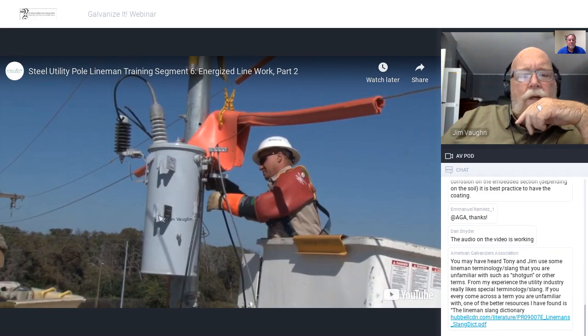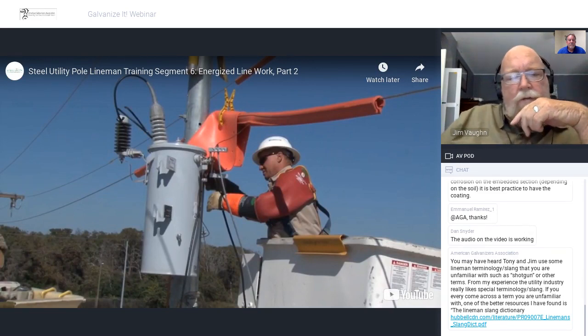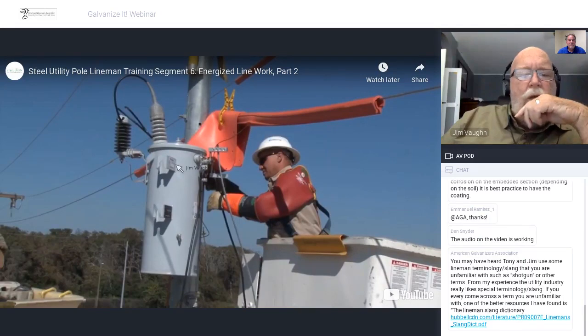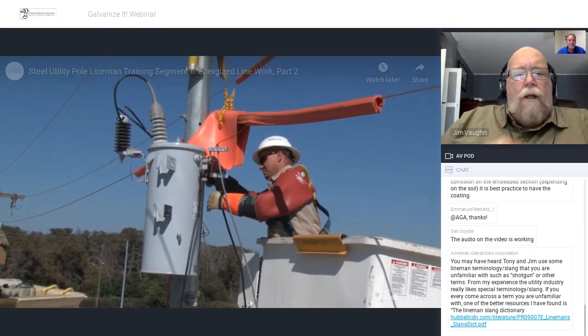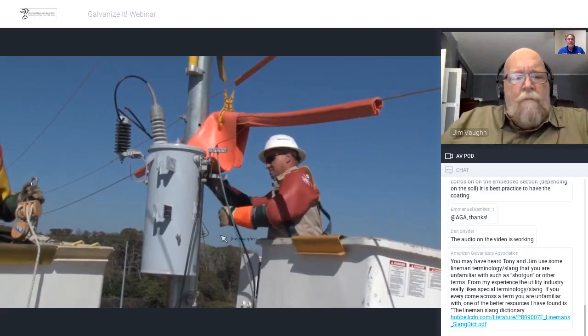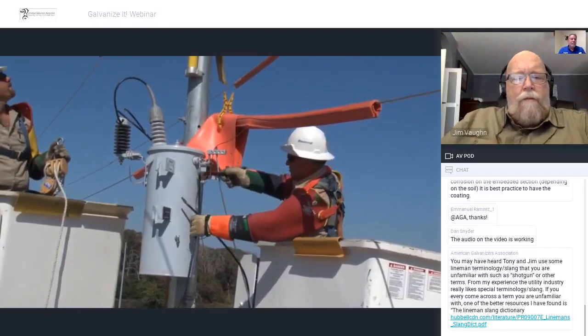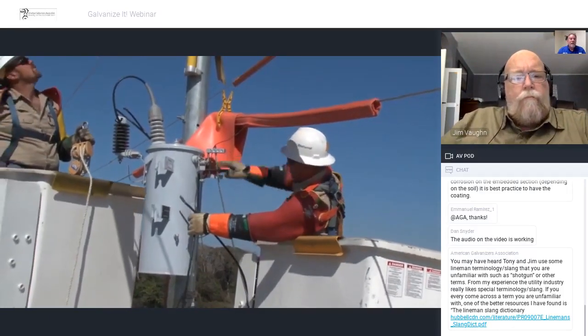This transformer looks like about a 15 kVA or 25 kVA transformer. It weighs about 400 to 500 pounds, depending on the core material that's made in there. So I just wanted to point that out for those of you who may not be familiar with the workings of distribution. Once these leads are disconnected, the only remaining connection is the case ground. The ground is always the last wire to come off.